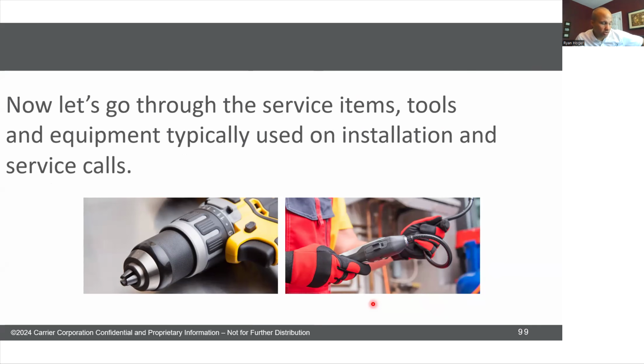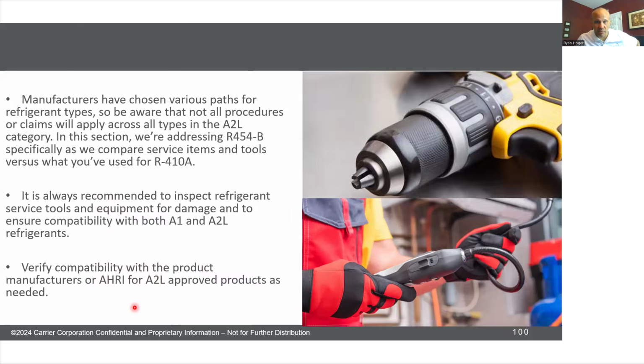Any tools that you're going to use around A2L refrigerants need to be non-sparking tools. So if you have a drill and it's old school and it has sparks shooting out the side, probably got to stop using that on the A2L job. All right. If you have a brushless DC motor in your drill, like 99% of you have, you're probably just fine. No new action taken, right? So things that have motors in them, we have to pay attention to those kind of things.